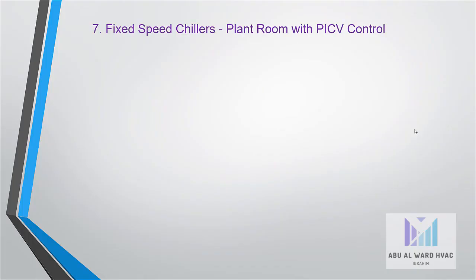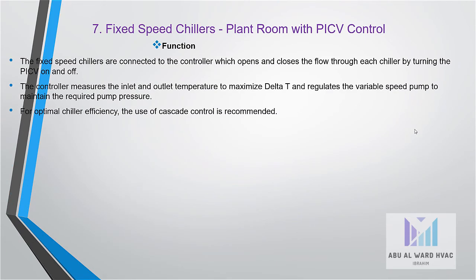Fixed speed chillers, plant room with PICV. The function: the fixed speed chillers are connected to the controller, which opens and closes the flow through each chiller by turning the PICV on and off. The controller measures the inlet and outlet temperature to maximize Delta T and regulate the variable speed pump to maintain the required pump pressure. For optimal chiller efficiency, the use of cascade control is recommended.